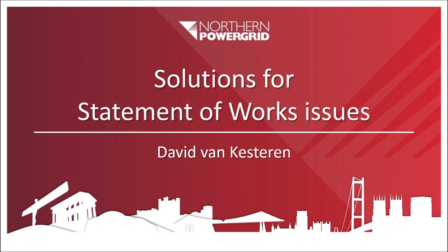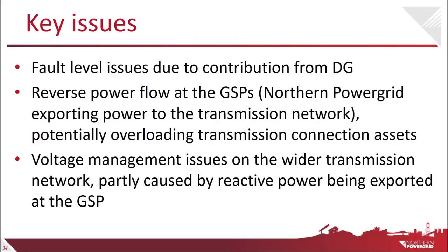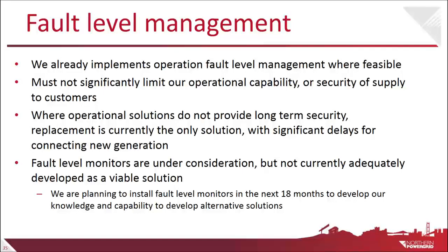So solutions for statement of works. As Kaz has outlined, we've got 3 potential issues that come out of statement of works normally. One is fault level, due to the fault level contribution from the distributed generation in the network. The second one is to do with the reverse power flow at the grid supply points due to the amount of generation in our network being greater than the amount of demand at the time. And then the third point is about the voltage management issues on the transmission network, which is partly caused by the reactive power that's being exported from our network through the grid supply point.